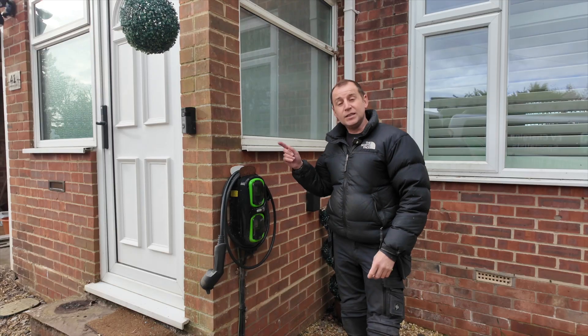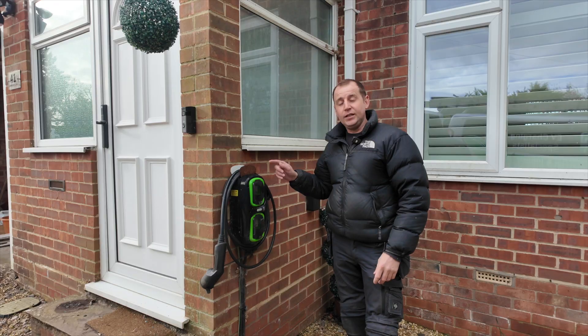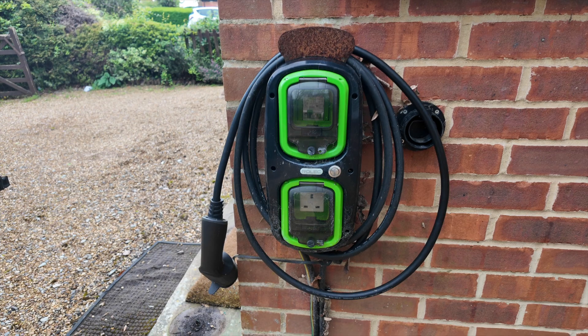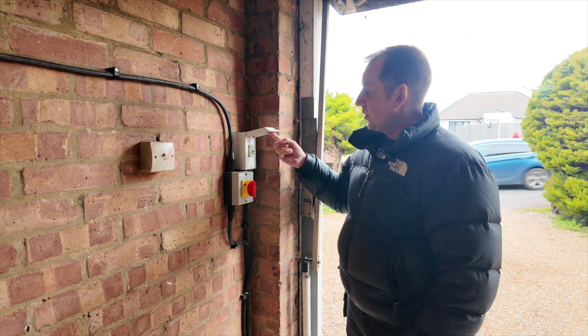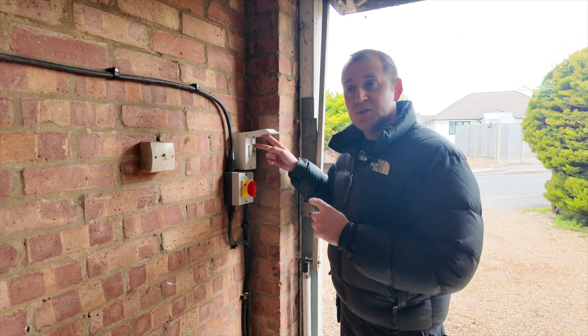This Rolec does not work. It is broken for the second time. My customer has had enough and frankly the installation is shocking. We have an EV isolator here and a little 13 amp socket C16 RCD for the 13 amp socket in the Rolec.